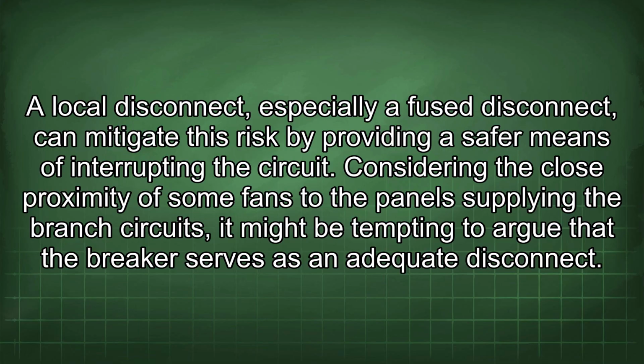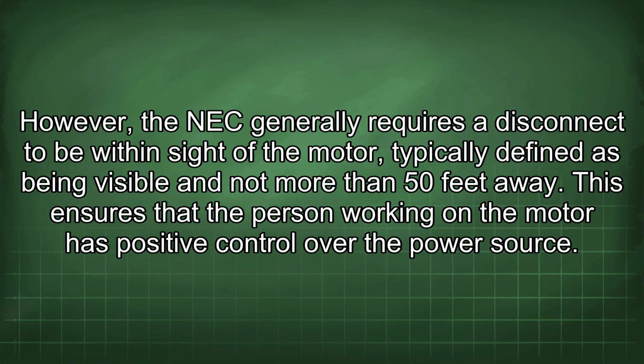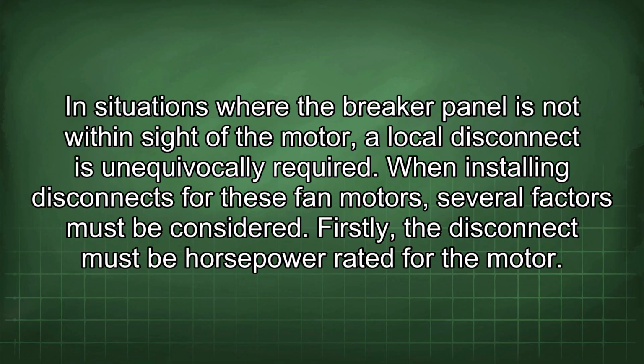Considering the close proximity of some fans to the panel supplying the branch circuits, it might be tempting to argue that the breaker serves as an adequate disconnect. However, the NEC generally requires a disconnect to be within sight of the motor, typically defined as being visible and not more than 50 feet away. This ensures that the person working on the motor has positive control over the power source. In situations where the breaker panel is not within sight of the motor, a local disconnect is unequivocally required.